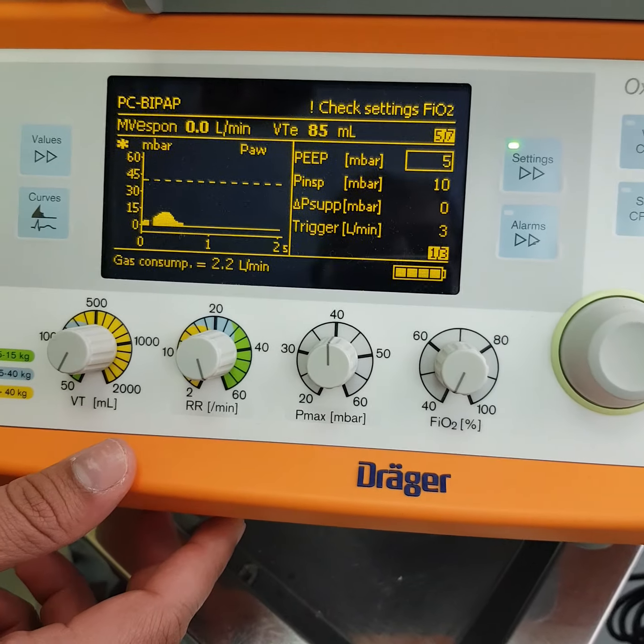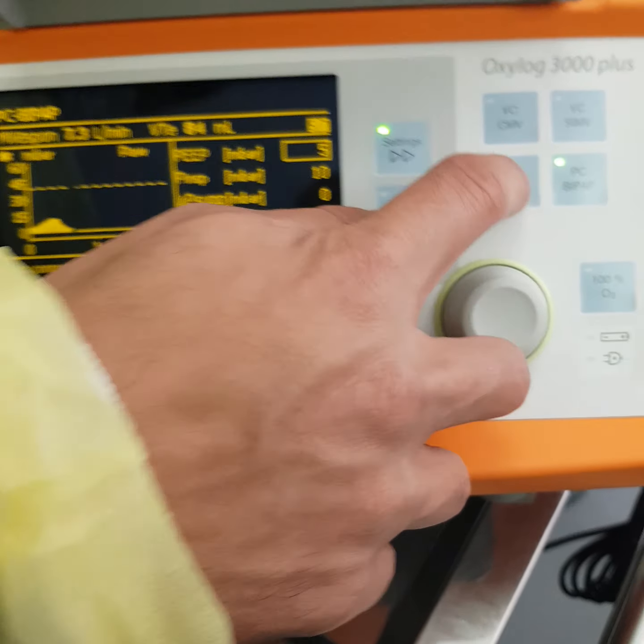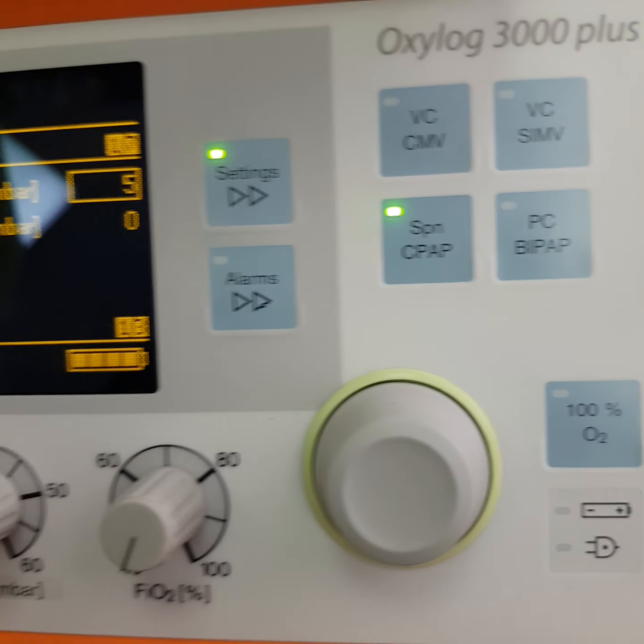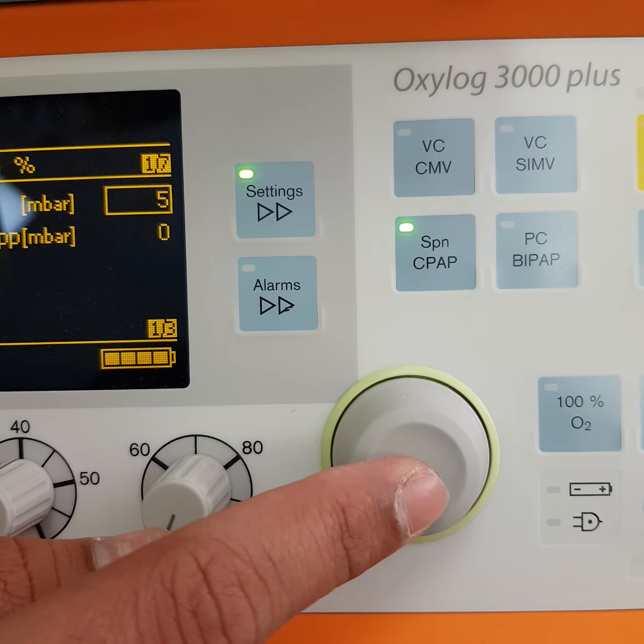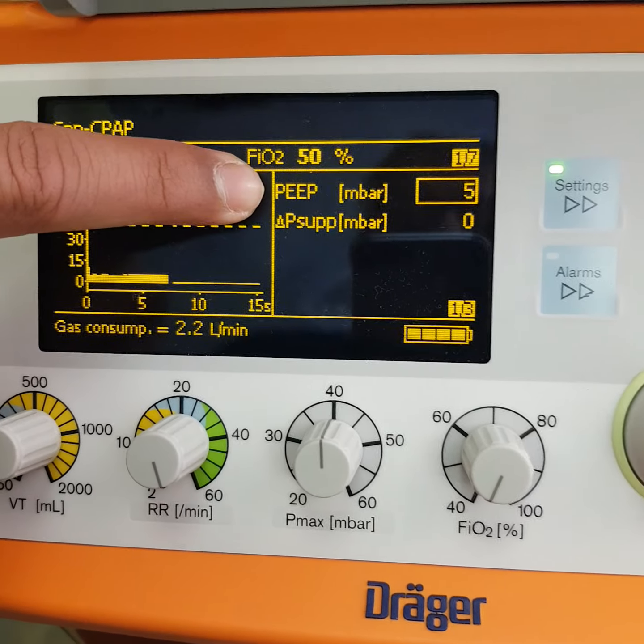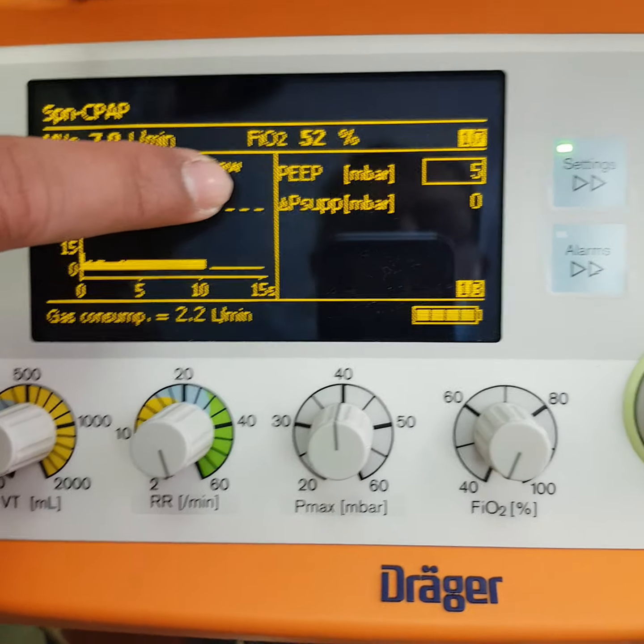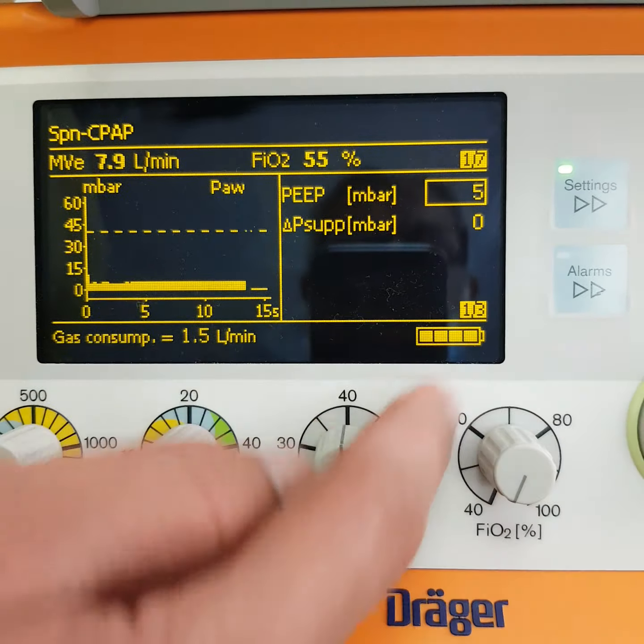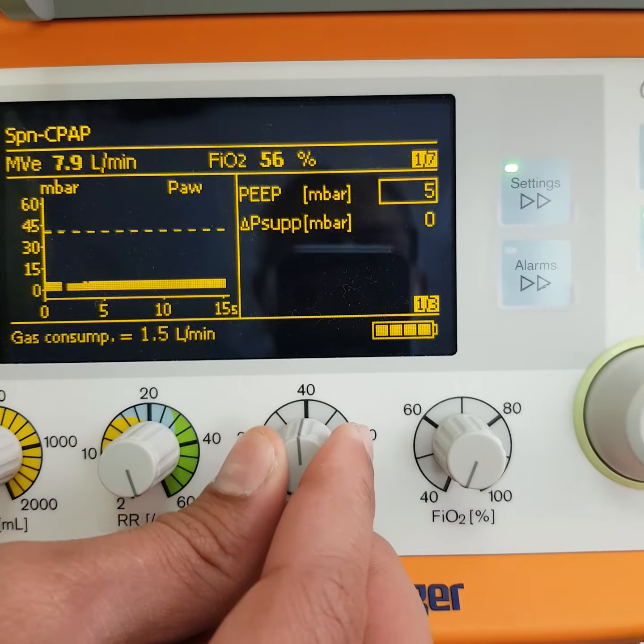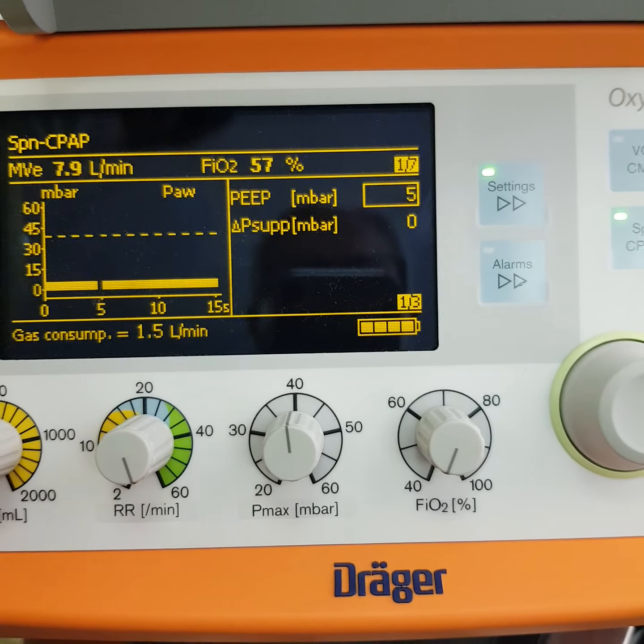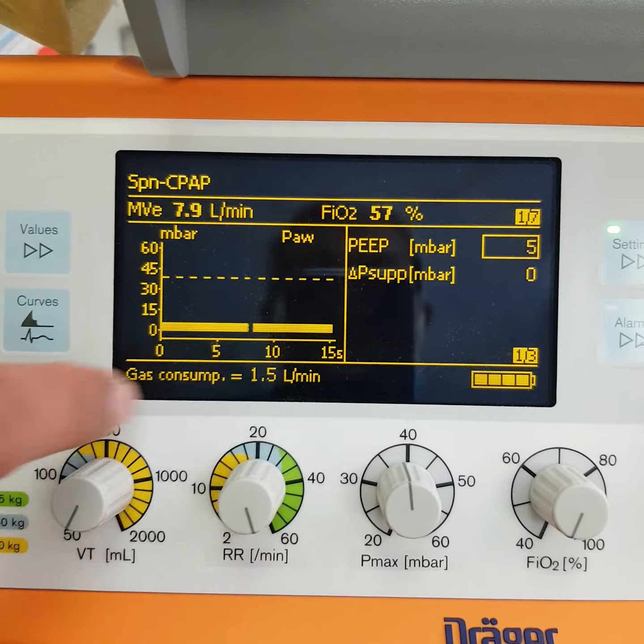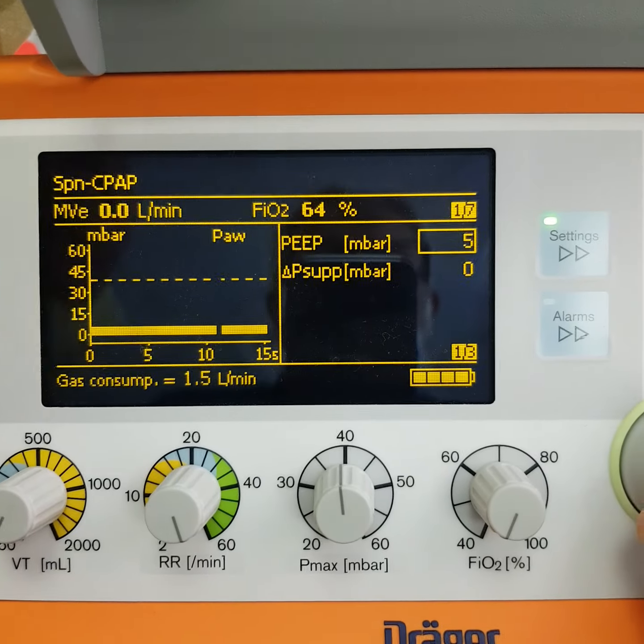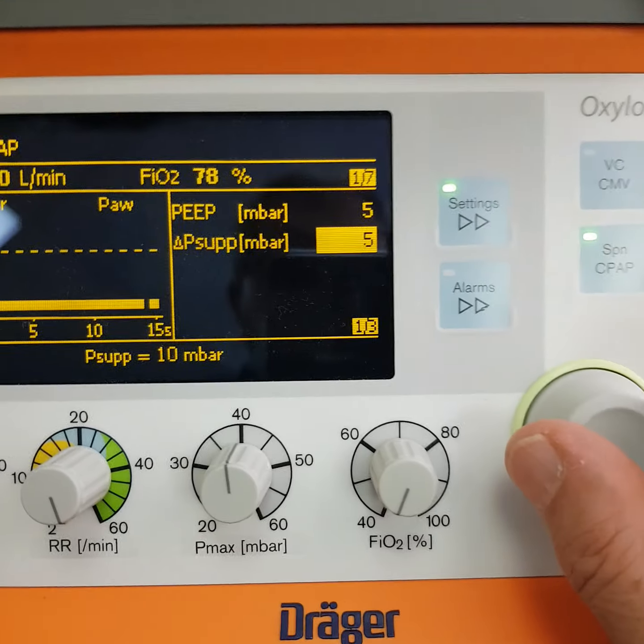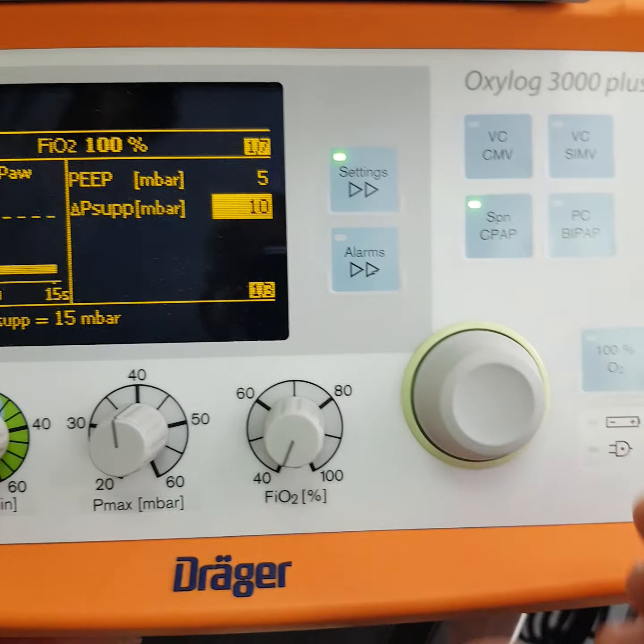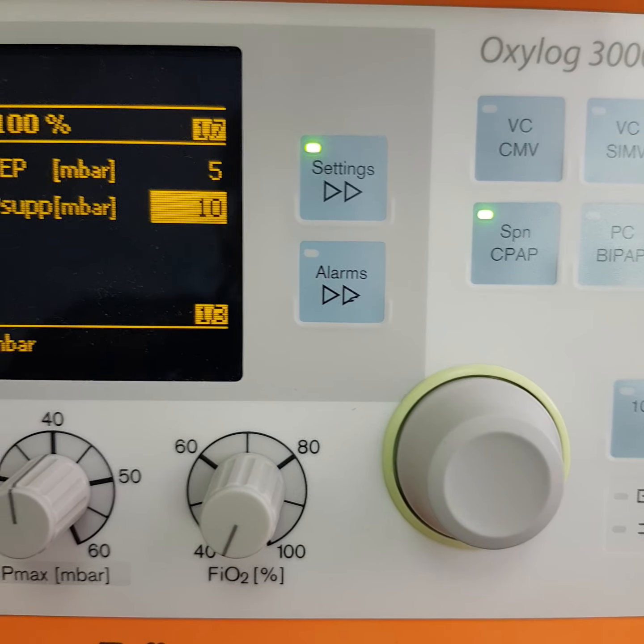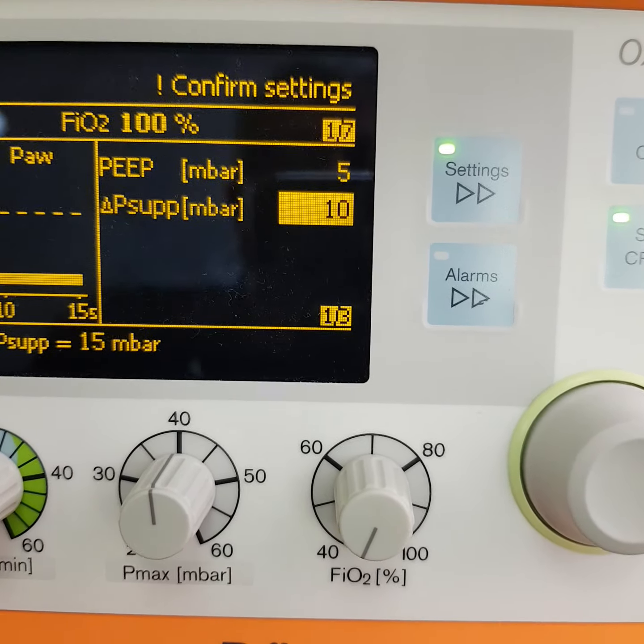If you want to do any other settings, you can use it for CPAP as well. If you want to shift to CPAP, you just select the mode and confirm with the knob. You are going to do a setup here with the PEEP, and pressure support is the only parameter that you can adjust. Other than that, there is the oxygen percentage. Pressure maximum can also be activated, but these two parameters will be deactivated, which are tidal volume and respiratory rate, because CPAP all depends on the patient's values. But you can activate some pressure support if the patient stimulates a spontaneous breath. We are on spontaneous CPAP with PEEP 5 and pressure support 10.